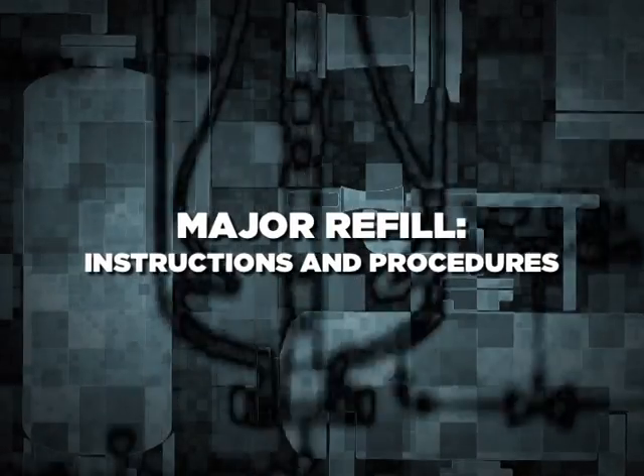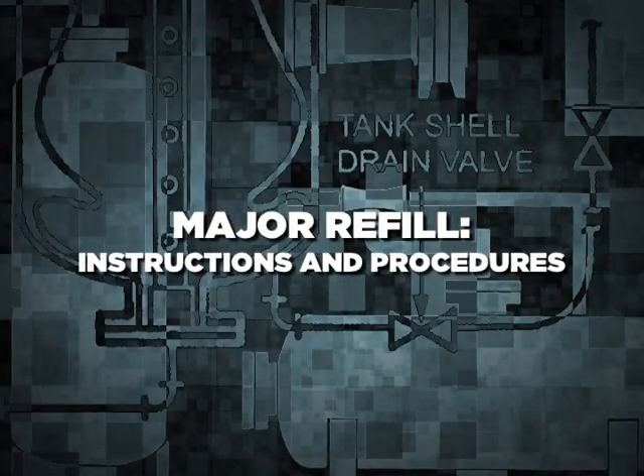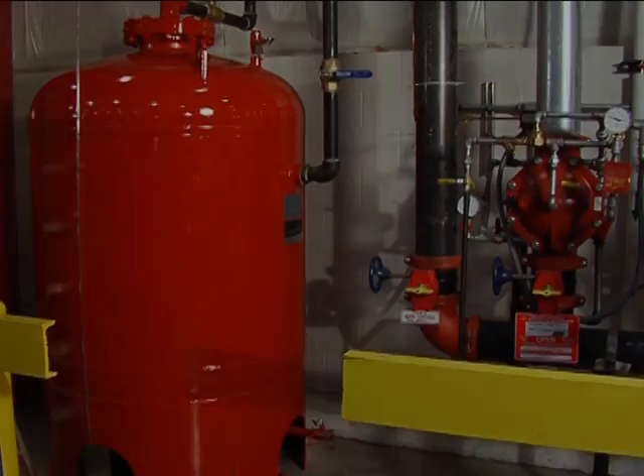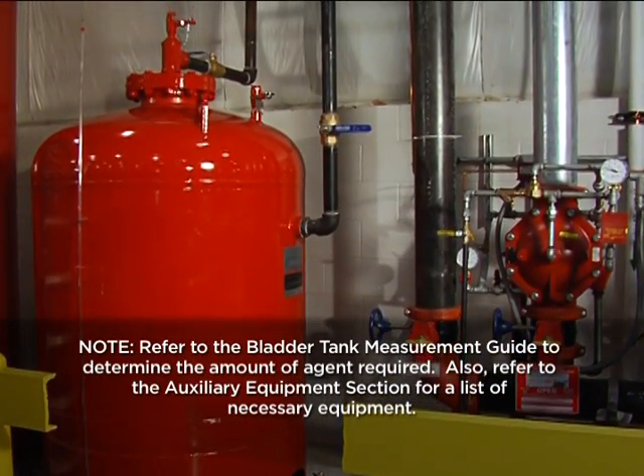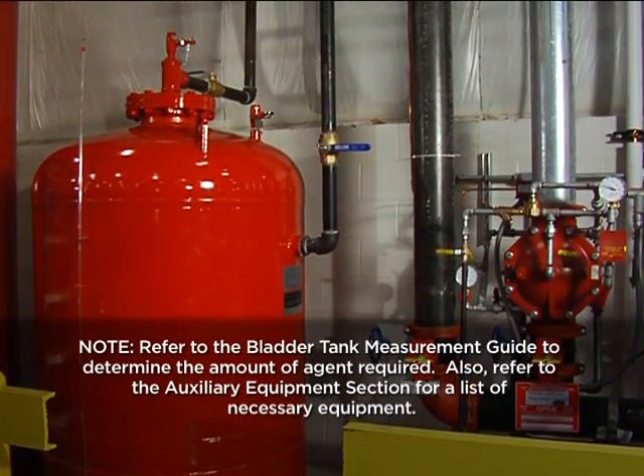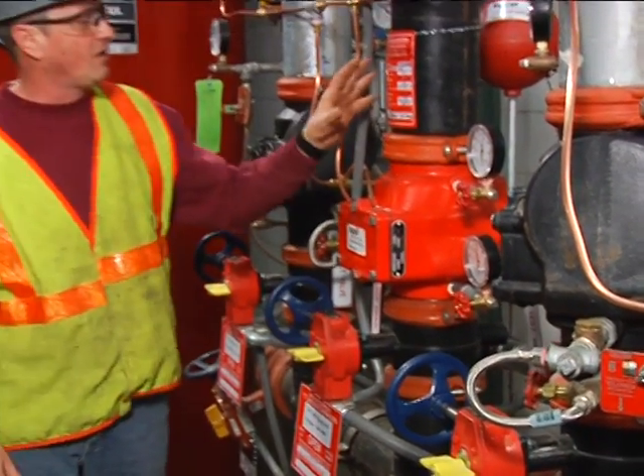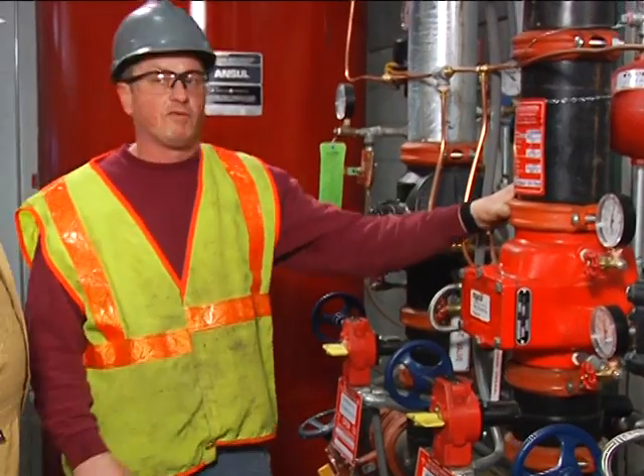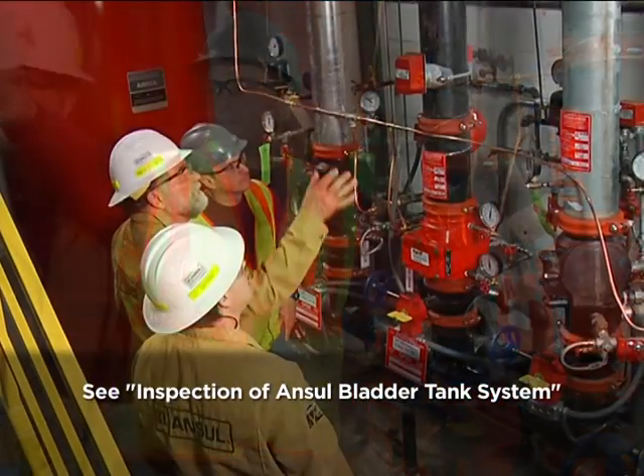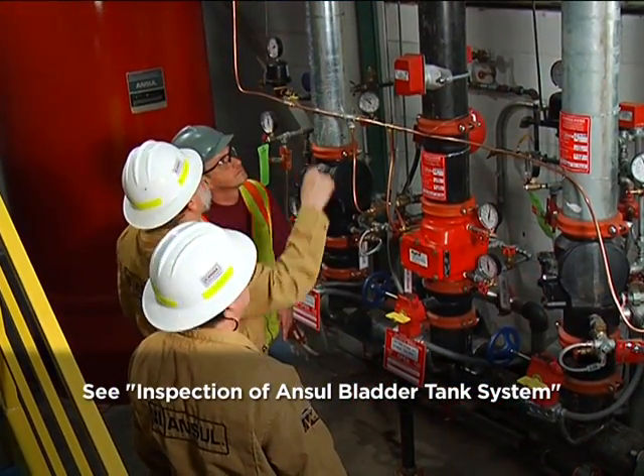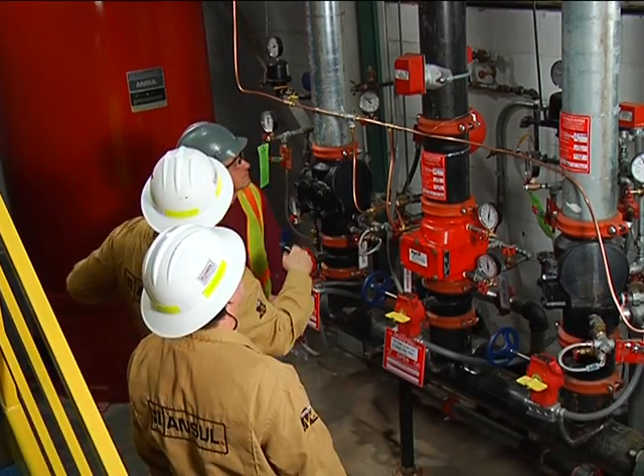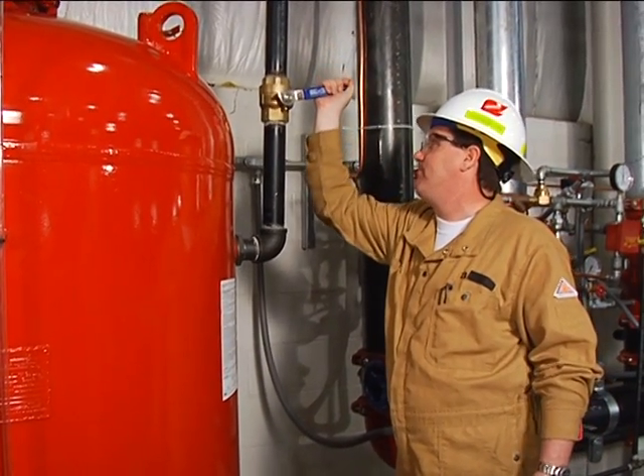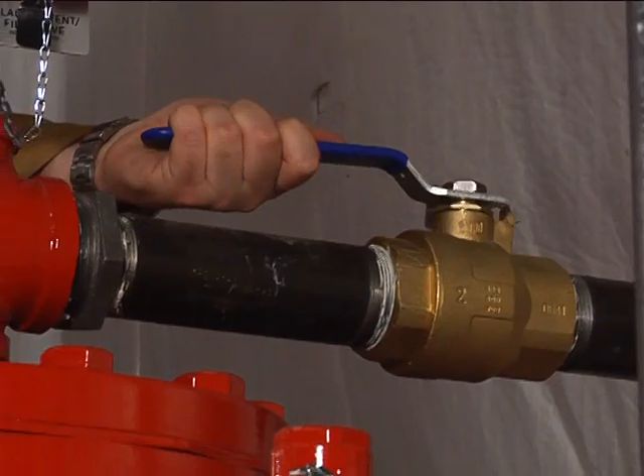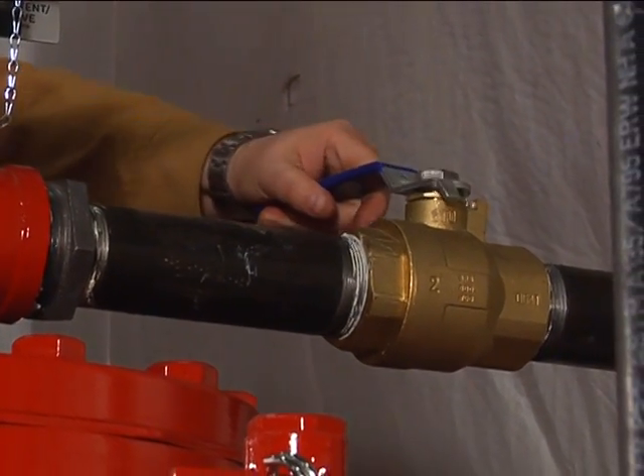Major refill, instructions and procedures. A major refill is required when more than 25% of the concentrate must be replaced within the bladder tank. Before you proceed with the initial fill, Ansul recommends performing a complete inspection of your Ansul bladder tank system. To refill the bladder tank, first close the water inlet valve and the concentrate isolation valve.